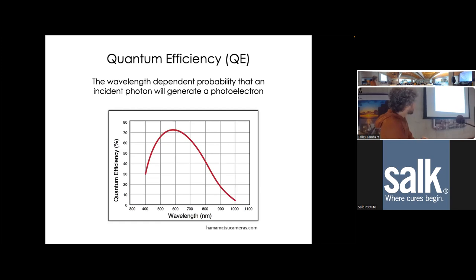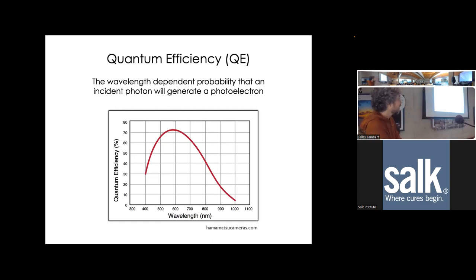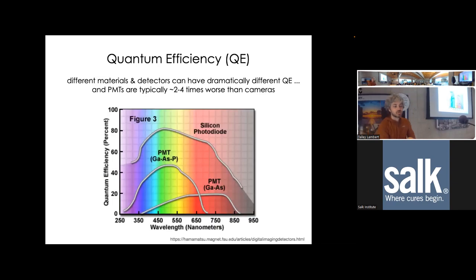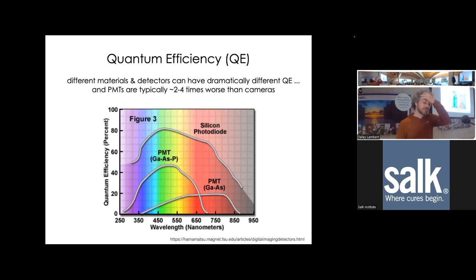It's very important to look at the quantum efficiency of your detector, particularly if you're imaging in the far red regime - make sure you're using a detector that is actually sensitive to that. Note that this does not mean the detector has color sensing capability. This is a monochromatic detector with some probability of detecting a photon that varies depending on wavelength, but it cannot discriminate between a 500 and a 600 nanometer photon.